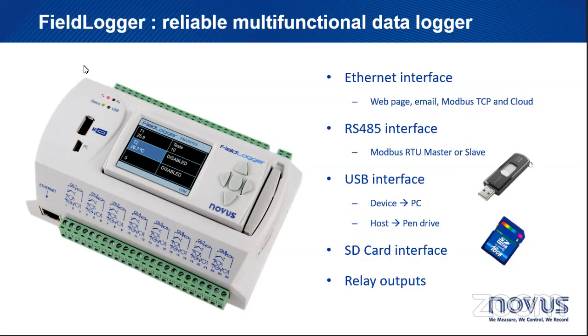So starting from the Ethernet interface, which is the higher level one, what does the FieldLogger do with the Ethernet? Well, it can serve an HTTP web page. It can send email alarms, okay? It can be a Modbus TCP IP server, which means if you have a SCADA system that would like to inquire from the FieldLogger, it is possible, okay? It is a server on Modbus TCP. It will also operate as a Modbus TCP to Modbus RTU gateway, okay? We'll see that later too. And also it allows you cloud connectivity.